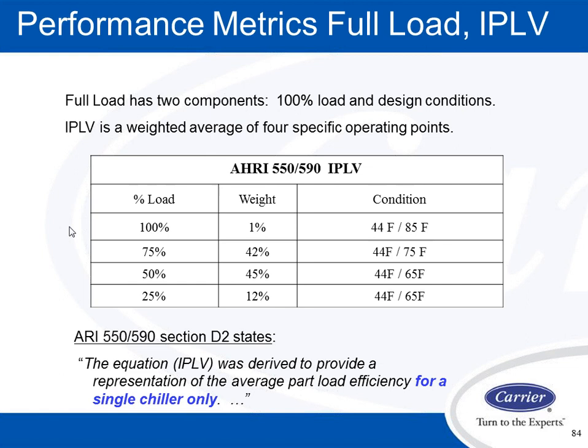So let's look at the IPLV matrix. Again, the full load has 2 components, 100% load and design conditions. IPLV is weighted in the following factor. The 100% load point, which they say happens 1% of the year, operates with 44 leaving and 85 entering condenser water. The 75% load point is weighted at 42%, with 44 degree water and 75 degree entering condenser water. The 50% load point has 45% of the hours weighted to it, 44 leaving, 65 entering. And the 25% load point has 12% of the hours weighted, 44 leaving, 65 entering.